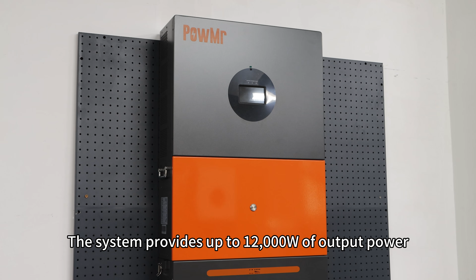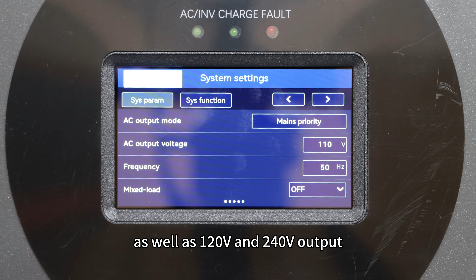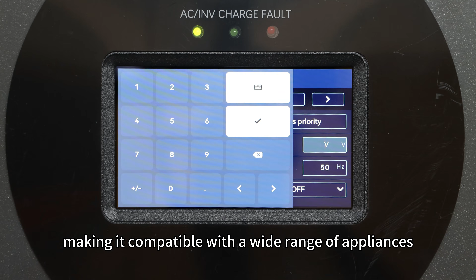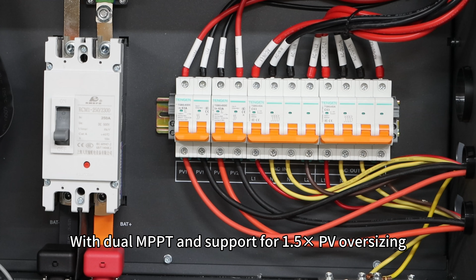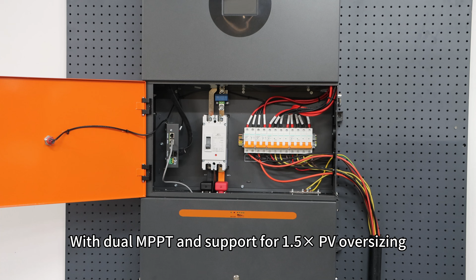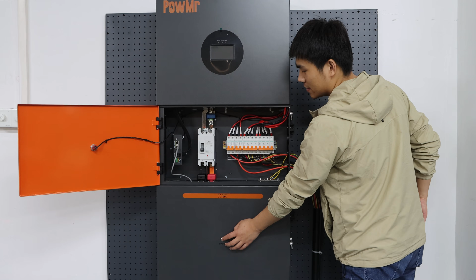The system provides up to 12,000 watts of output power. It supports 100 to 127V adjustable voltage, as well as 120V and 240V output, making it compatible with a wide range of appliances. With dual MPPT and support for 1.5 times PV oversizing, the system captures more solar energy throughout the day. After all wiring is complete, turn on the battery switch.